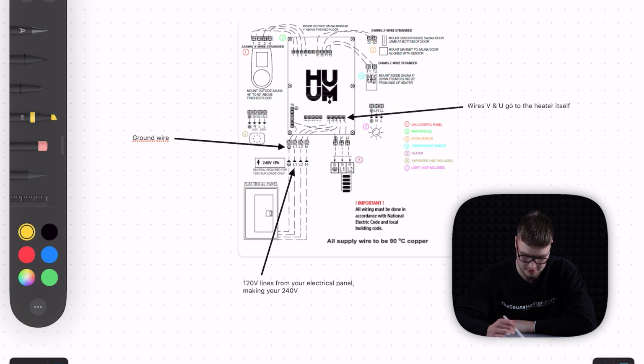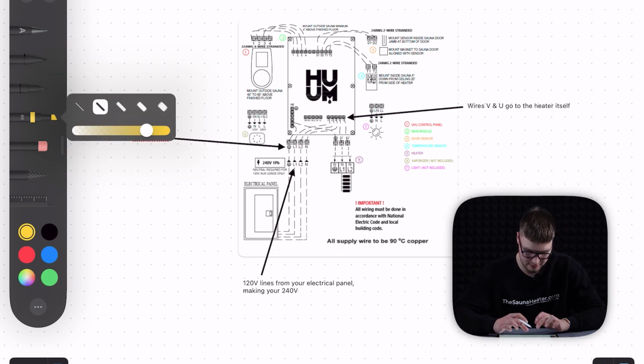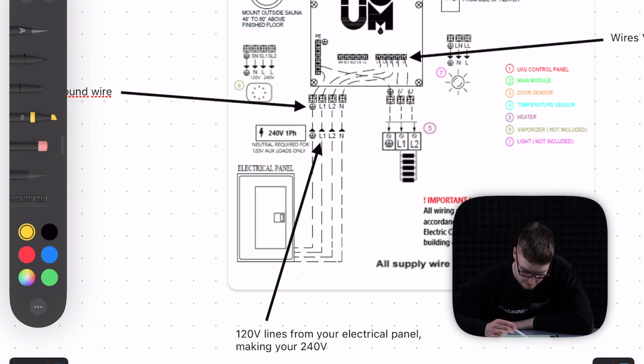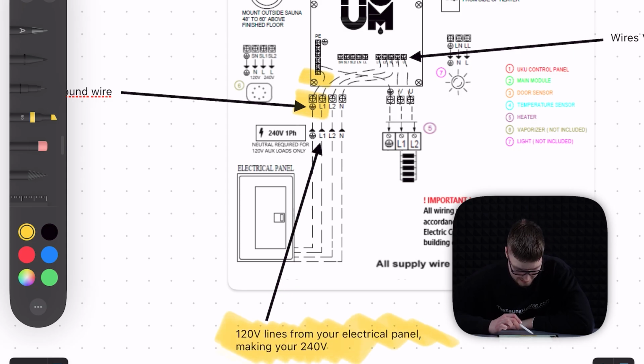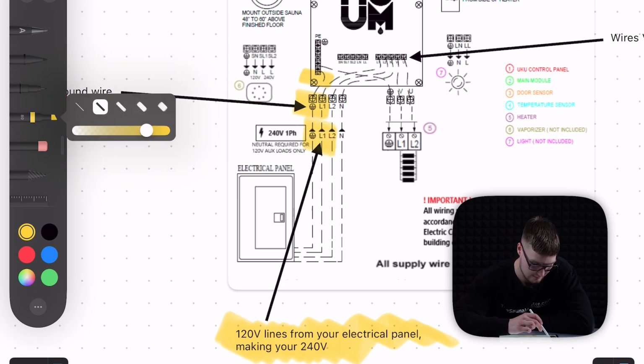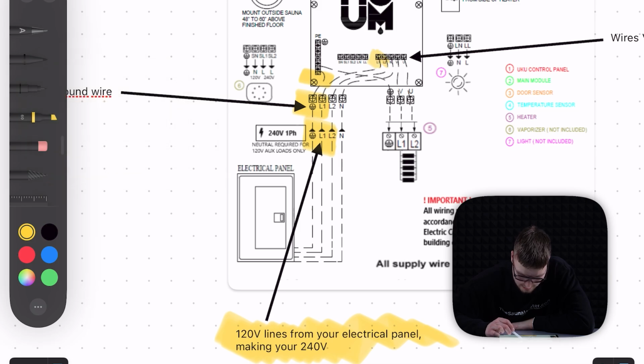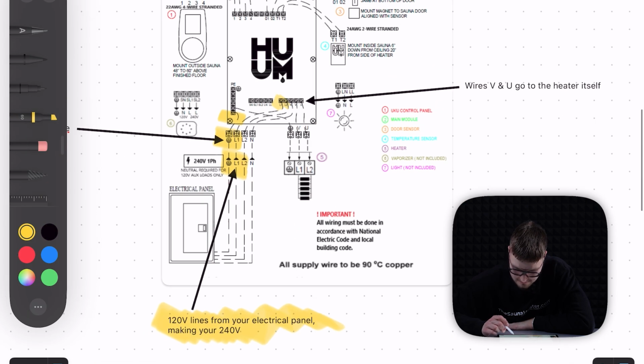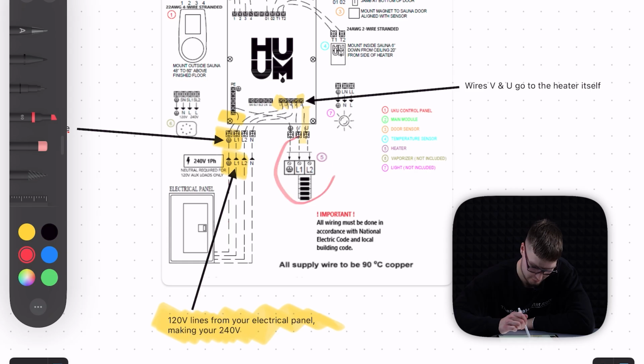Here you can see HUUM's wiring diagram. This ground wire goes from your electrical panel to the ground connection. Then we have 120 volt lines from your electrical panel, L1 and L2, which together make 240 volts. These L1 and L2 lines go to L1 and L2 right there. Otherwise we have wires V and U next to wires L1 and L2 that go to the sauna heater itself. This presents the connections on the bottom of the sauna heater. That's how HUUM's wiring works.